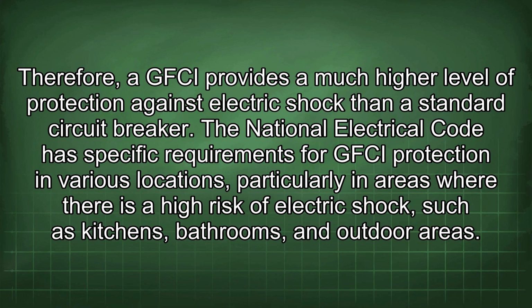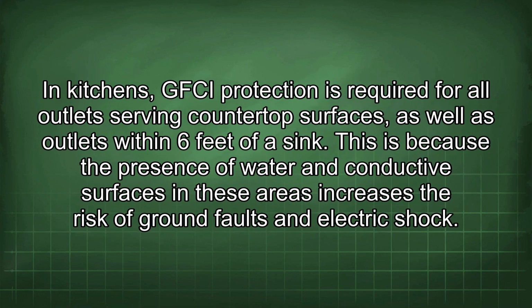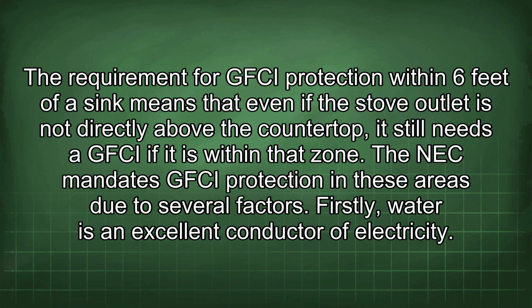The National Electrical Code has specific requirements for GFCI protection in various locations, particularly in areas where there is a high risk of electric shock, such as kitchens, bathrooms, and outdoor areas. In kitchens, GFCI protection is required for all outlets serving countertop surfaces, as well as outlets within 6 feet of a sink. This is because the presence of water and conductive surfaces in these areas increases the risk of ground faults and electric shock. The requirement for GFCI protection within 6 feet of a sink means that even if the stove outlet is not directly above the countertop, it still needs a GFCI if it is within that zone. The NEC mandates GFCI protection in these areas due to several factors.